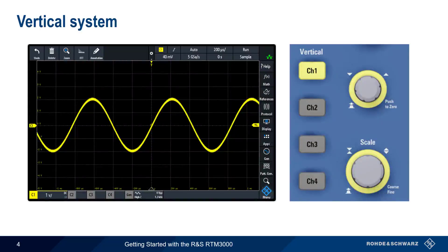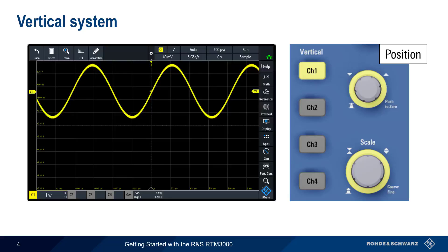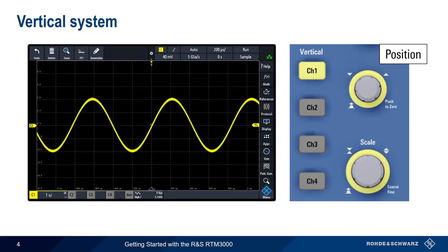The vertical system controls consist of the Position knob and Volts Per Division or Vertical Scale knob. The Position knob can be used to move the waveform up and down, and pushing the knob recenters the waveform. Volts Per Division is used to scale the waveform vertically. The current value of Volts Per Division is shown at the bottom and can of course also be read directly off the vertical axis.